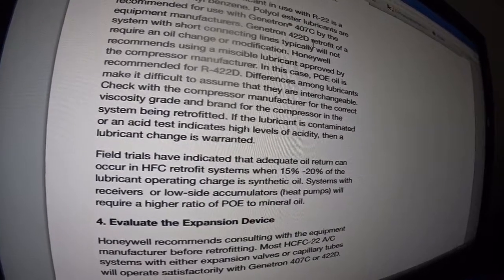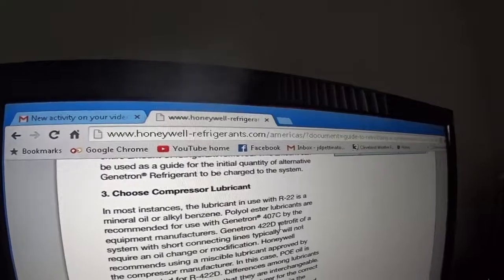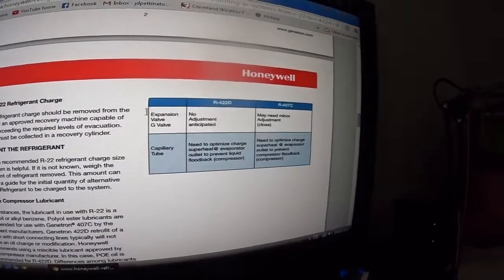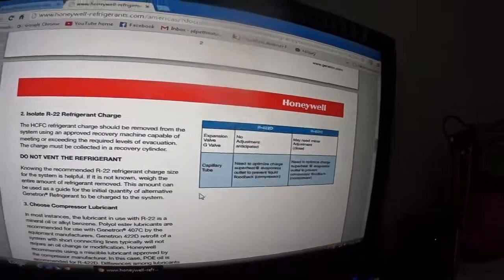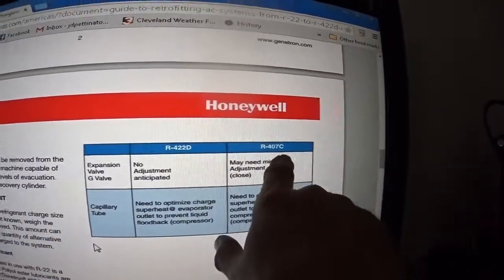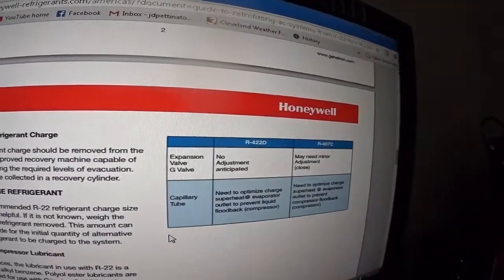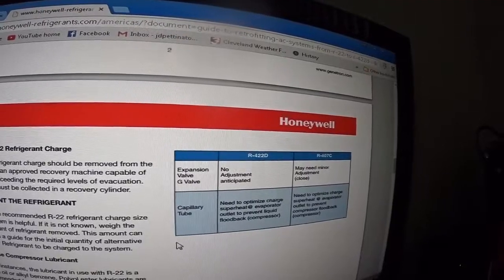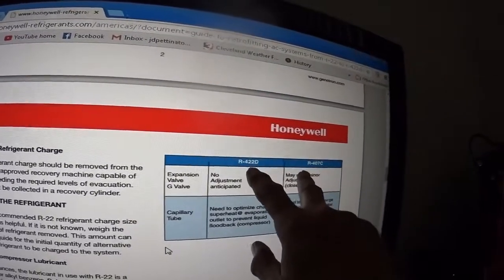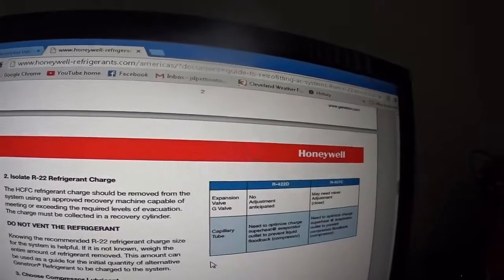I'll put the Honeywell link in the description so you can find this site. This may not even be the newest link, but this website is fundamentally talking about retrofitting from R22 to 422D or 407C, which both work fairly well. It's kind of like switching from regular milk to almond milk — it's different, but it gets the job done. You're moving from HCFC to HFC in the system, which is where everything is going.